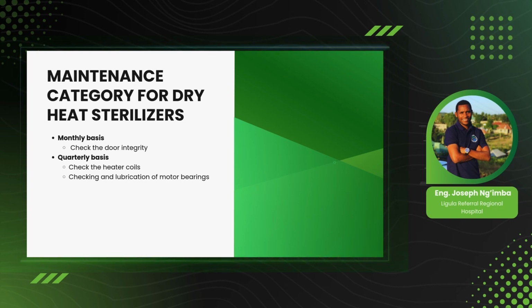Okay. Those things that I was discussing with you that we do in maintenance, I have categorized them in 3 categories: those we do on a monthly basis, those we do on a quarterly basis, and those we do on a 6-month, semi-annual basis. Here I highlighted that on a monthly basis on these dry heat sterilizers, we check the door integrity, the gasket, and clean the chamber. On a quarterly basis, you can check the heater coil, check the lubrication, and check if it is necessary to lubricate the bearing of the fan.